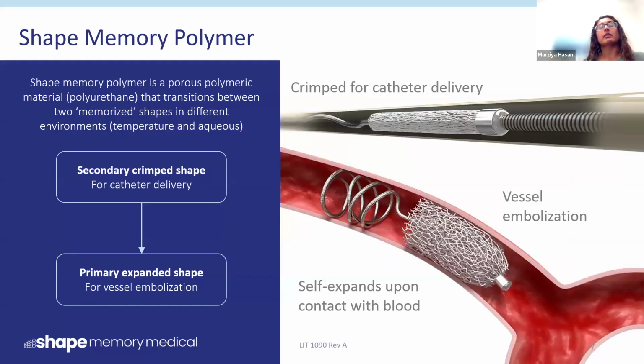So our key technology is our devices being self-expanding. We have a critical component, which is a shape memory polymer. It's a porous foam that can transition between 2 different shapes. We can program this material into a small geometry that can then be deployed through a catheter. So from a medical device perspective, we are able to take our shape memory polymer plug and crimp it to a small cylindrical rod geometry, which it can then be deployed really anywhere in the body using a catheter. Once our devices have exited the catheter and are in the vessel space, the foam component will slowly expand when it contacts blood, and it will cause embolization in whatever area that it's been deployed in.